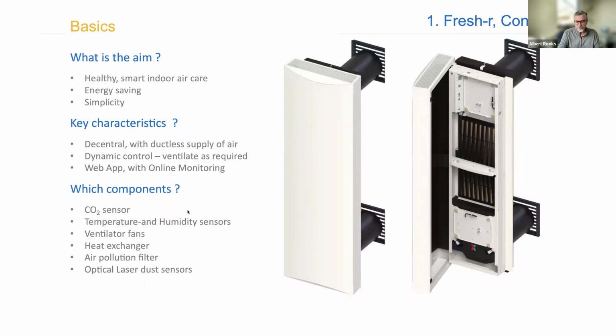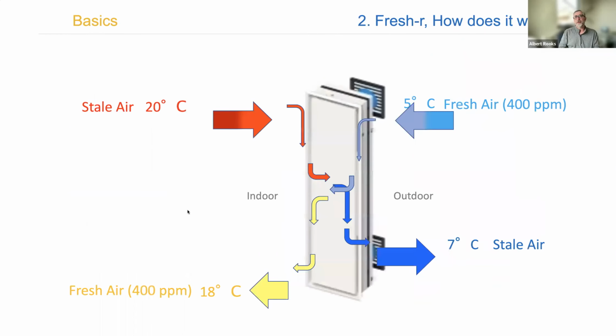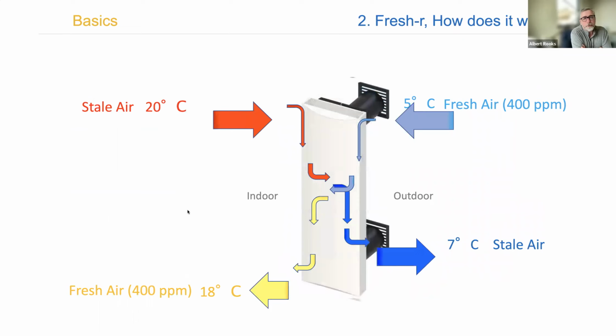design. And then there's a few features here which some people can take or leave, and that's the MERV 14 filter, and then optical laser dust sensors, which come into an interesting development. But basically, here's the way it works. We've got fresh air from the outdoors, upper right-hand side, and stale air from the room coming back at 20 degrees Celsius, which is roughly 70 degrees Fahrenheit. Fresh air is going through heat recovery. And so the supply flow in the yellow down on the lower left is sourced from the outside of the building, going across the heat exchanger. And it's getting about 85% recovery. That's usually about 85 to 90% recovery. That's that range. And so it's classic HRV. And really, it's just that white box sitting on the wall. I think we'll see a couple of applications of it.